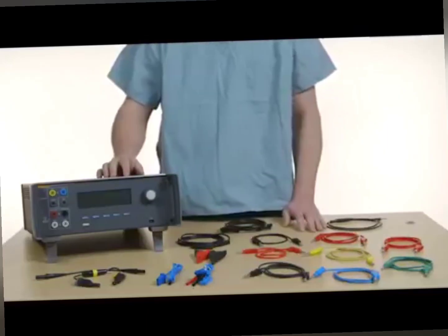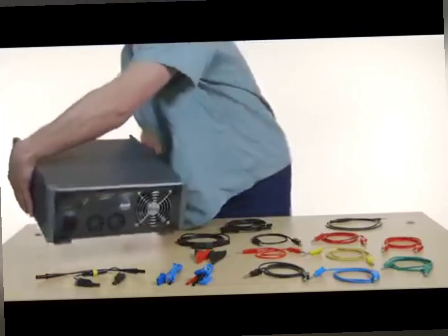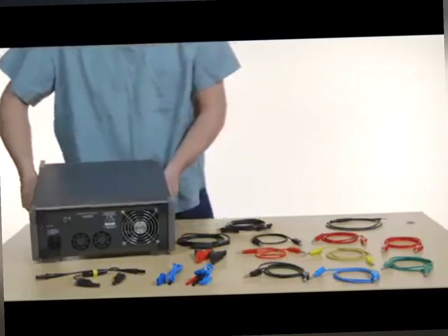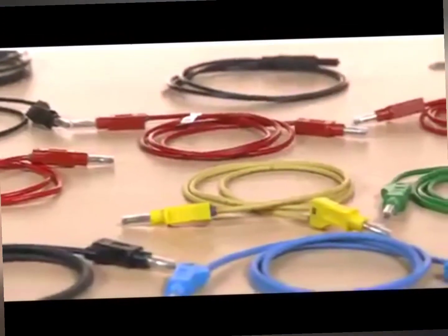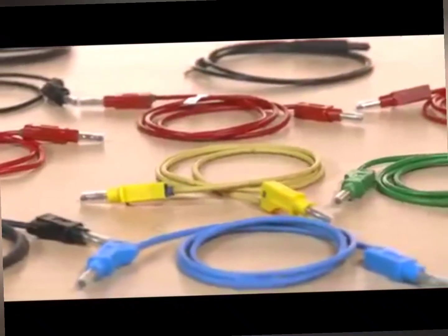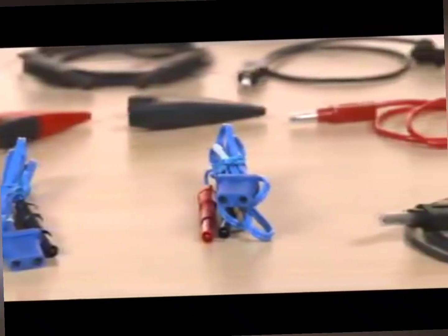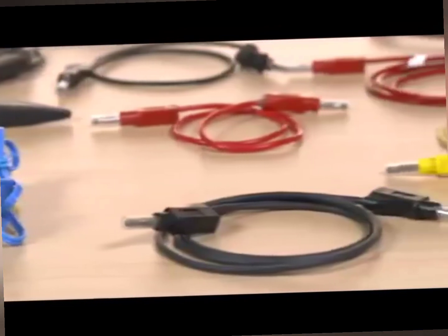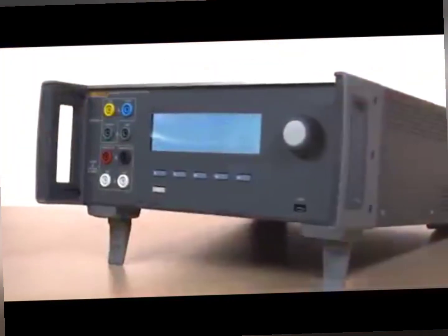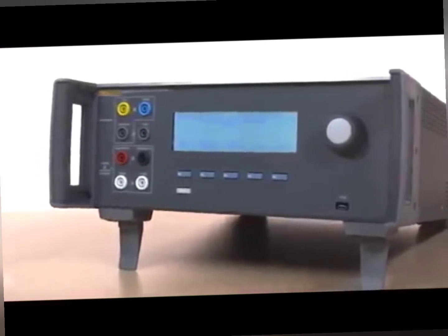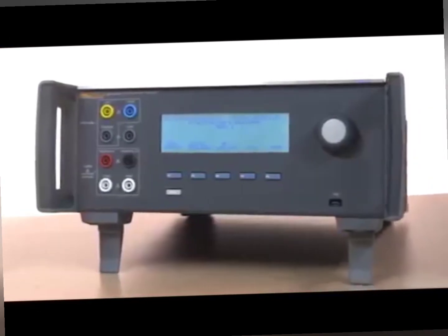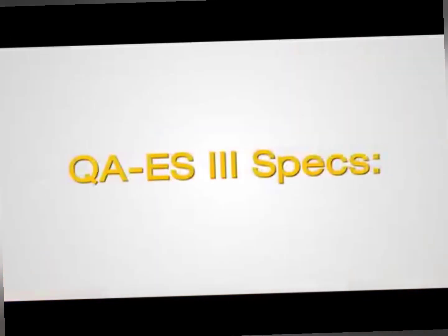When you pick up the QA-ES3, you'll quickly discover it's lighter than the previous version, 5.5 pounds lighter. Everything you need to test all critical functions of today's high-power electrosurgical units is either integrated into the design or included with the unit. There's no need for extra cables, leads, or switch boxes to test precision power, current, frequency, crest factor, and load resistance ranges. The state-of-the-art technology of the QA-ES3 provides exceptional accuracy and range of measurement. Its wide range of loads allows users to test the breadth of electrosurgical generators.